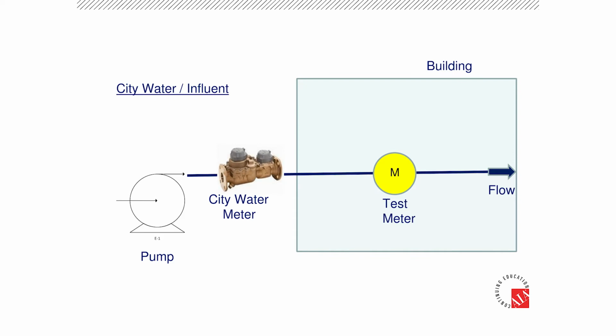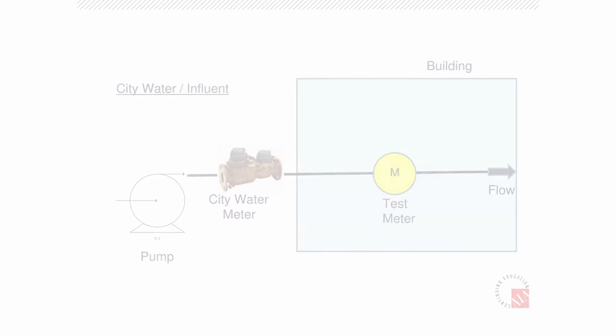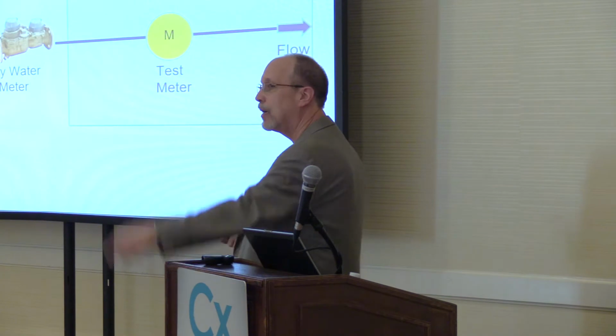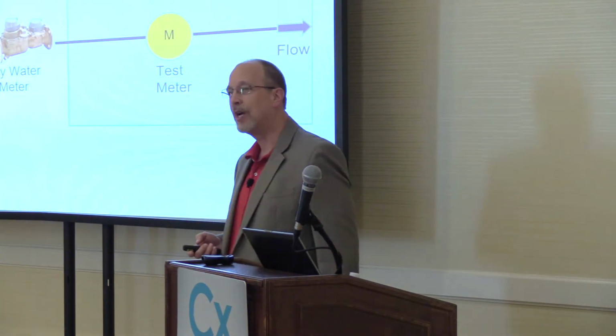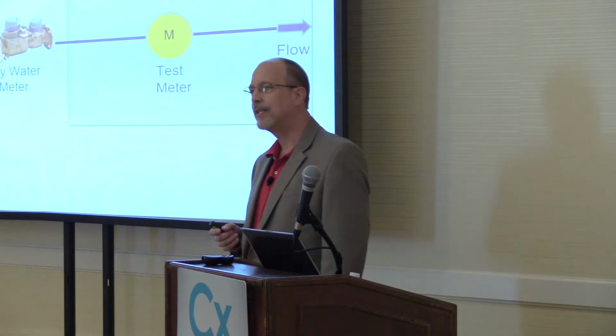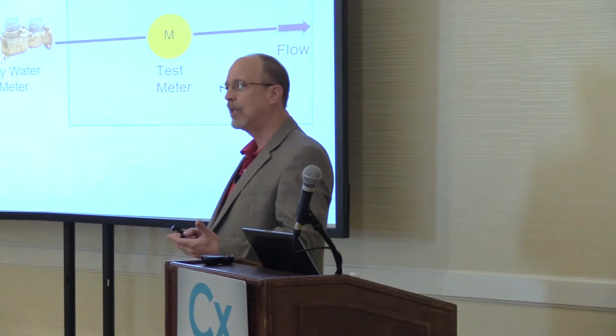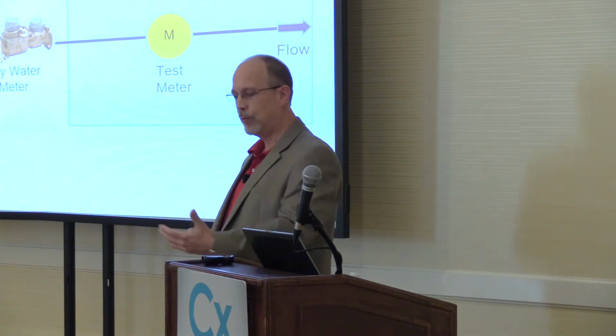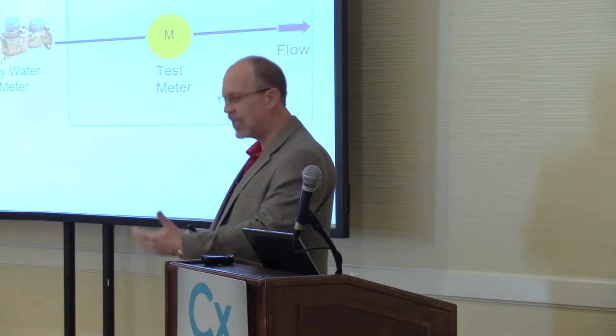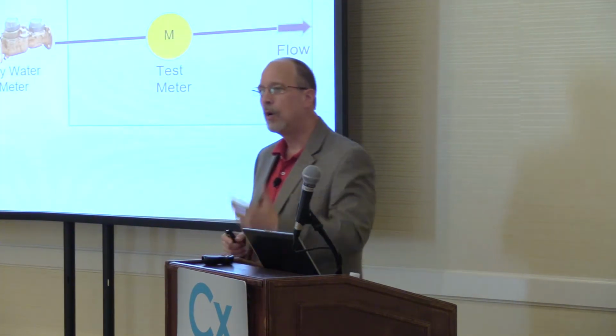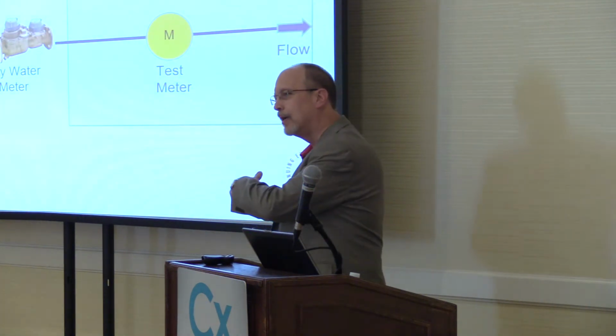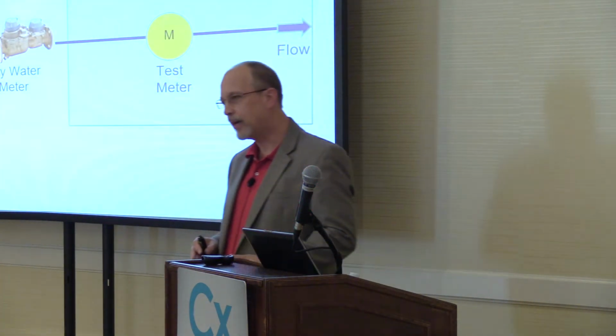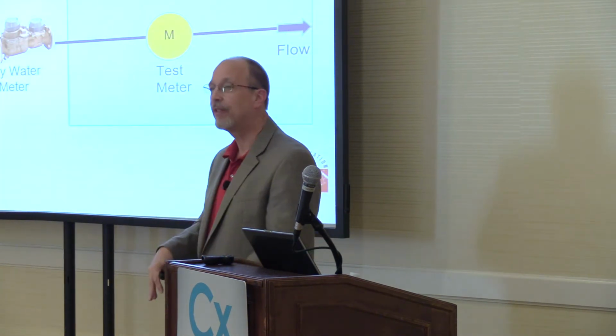So we have this big hotel, and I'm in the basement of a big hotel, and we've got a 10-inch water line, and he wants us to monitor against a city water meter. And so we go in the basement here, we throw this on this 10-inch line there, and he basically says, I'm going to go upstairs and turn the water on, and you put your flow meter on there and measure how much we got. No problem. He comes back there and says, how much did you see? We said, we didn't see anything. He said, well, let me go do it again. Comes back down to the basement, you still don't see it. He said, I flushed it twice, how come you didn't see it? He flushed the toilet, which was 6 gallons, in a 10-inch line, which equals something like 0.001 feet per second. I can't see that. It's too low of a flow rate.